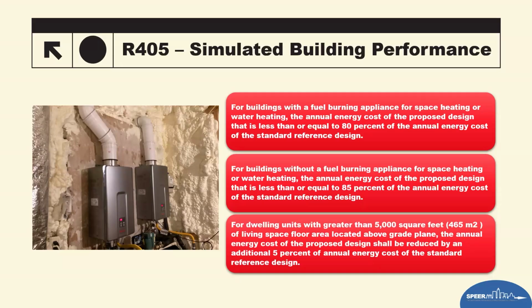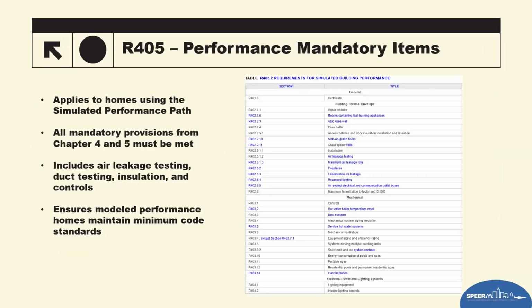It now focuses on a total annual cost of energy, rewarding designs that use less overall energy, regardless of how that savings is being achieved. So performance is one of the easiest and least costly pathways to get through Texas code. There still are performance mandatory items from the 2018 prior versions of the code. There were sections that were listed as mandatory. That has now ceased to exist. It's now a table of mandatory items.